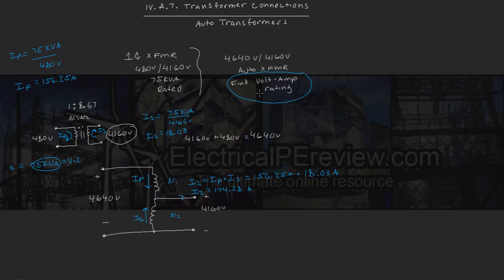So the problem is asking us find our volt amp rating. We're going to do this a couple different ways just to check our work and to prove each way works. So our volt amp rating S is equal to our voltage times our current for either our input side or our output side. So let's go on our input side first. Our autotransformer has an input of 4640 volts and 156.25 amps. Let's do the math, and we come up with 725 kVA.